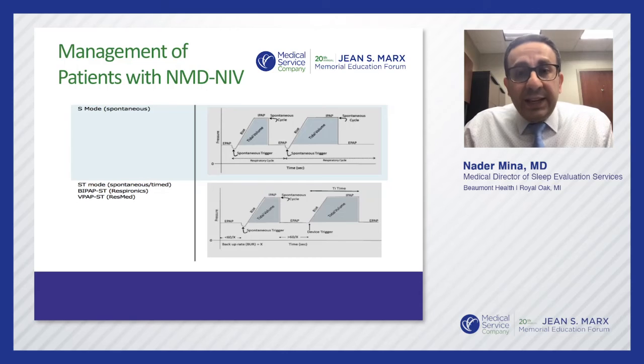The next couple of slides, we'll talk a little bit about some modes that we use on the respiratory assist device. This is the spontaneous mode. The key difference between the spontaneous and the spontaneous timed mode is actually the time for inspiration. In the first diagram, you have the first spontaneous breath where the patient triggers the breath, and the patient himself or herself determines the inspiratory time. They spontaneously cycle from the EPAP to IPAP and go back to the lower pressure, which is the EPAP. So the key feature of the spontaneous mode is that patients determine the appropriate time to cycle and the inspiratory time.